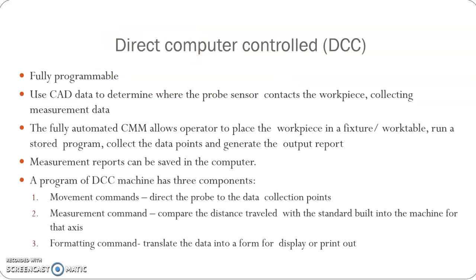In direct computer controlled or DCC, all the movements and all other functions are controlled by computer only. No manual intervention is there. Here we are using CAD data that was previously made. CAD data is fed to the machine and that will determine the path of the probe. The probe sensor will move and contact the workpiece surface, collecting measurement data. Everything will be controlled by the computer.